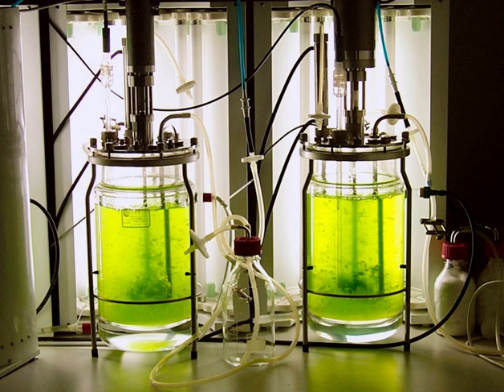Agitator, used for the mixing of the contents of the reactor which keeps the cells in perfect homogenous condition for better transport of nutrients and oxygen to the desired products. Baffle, used to break the vortex formation in the vessel, which is usually highly undesirable as it changes the center of gravity of the system and consumes additional power. Sparger, in aerobic cultivation process, the purpose of the sparger is to supply adequate oxygen to the growing cells. Jacket, the jacket provides the annular area for circulation of constant temperature of water which keeps the temperature of the bioreactor at a constant value.